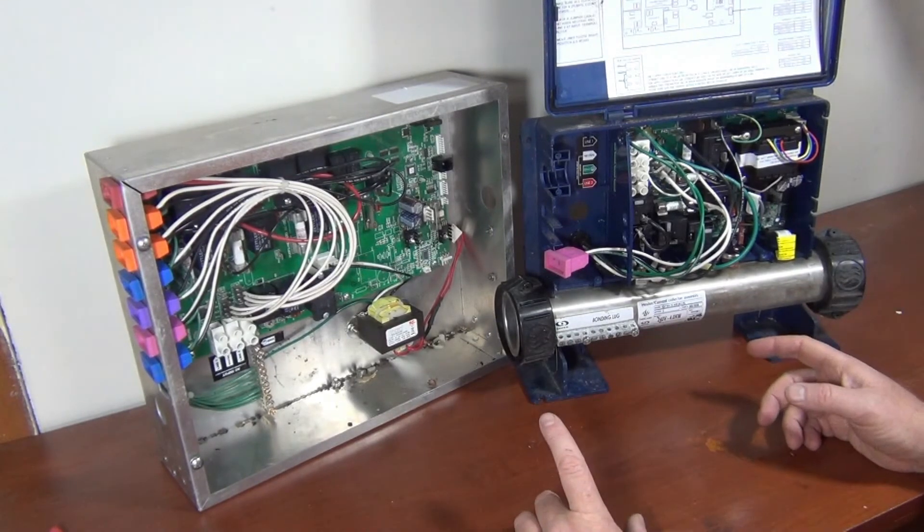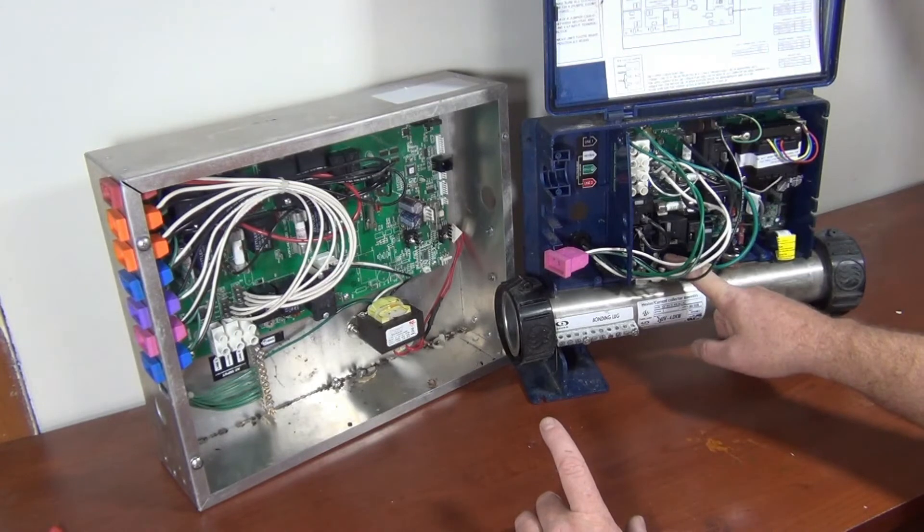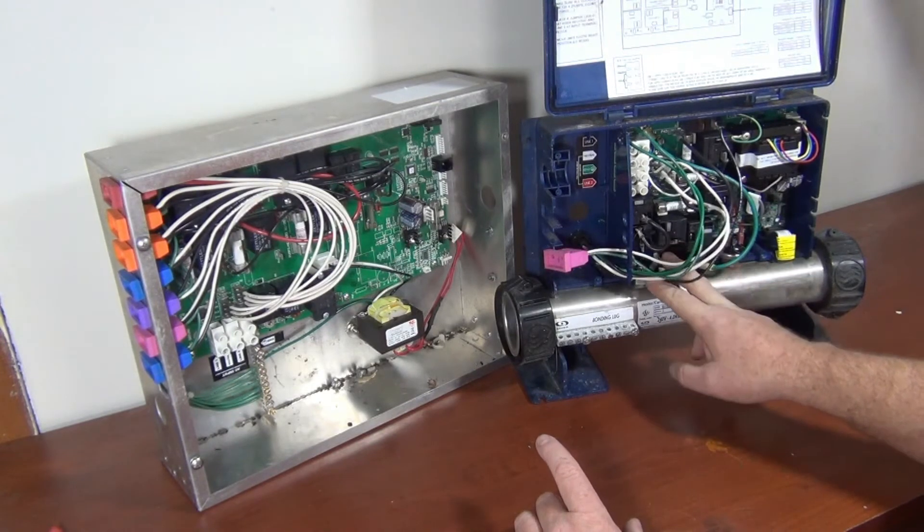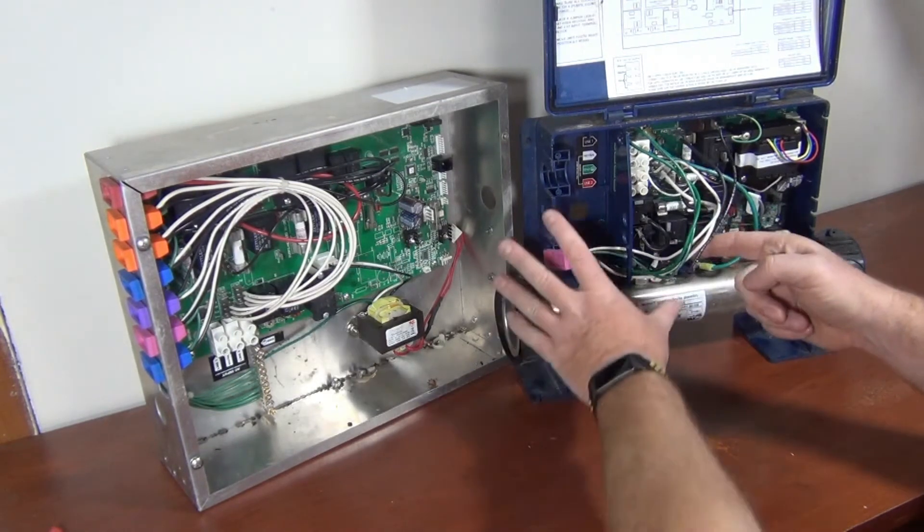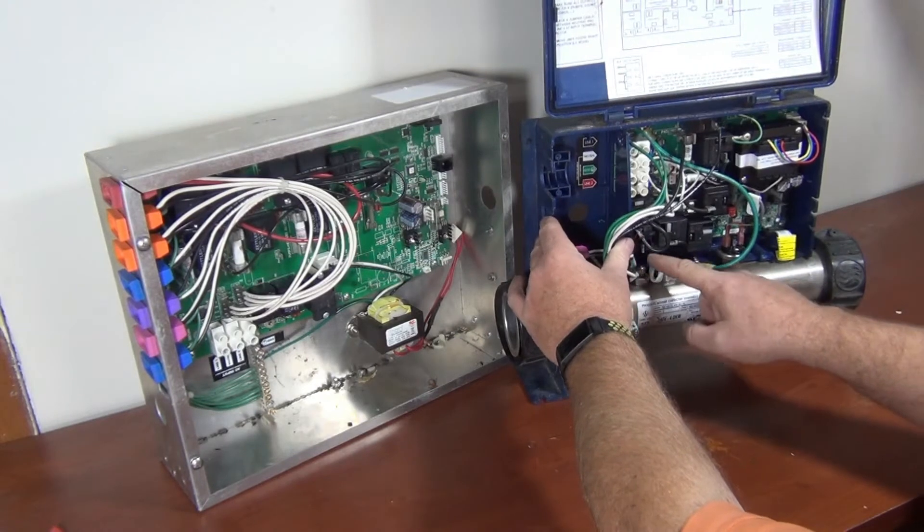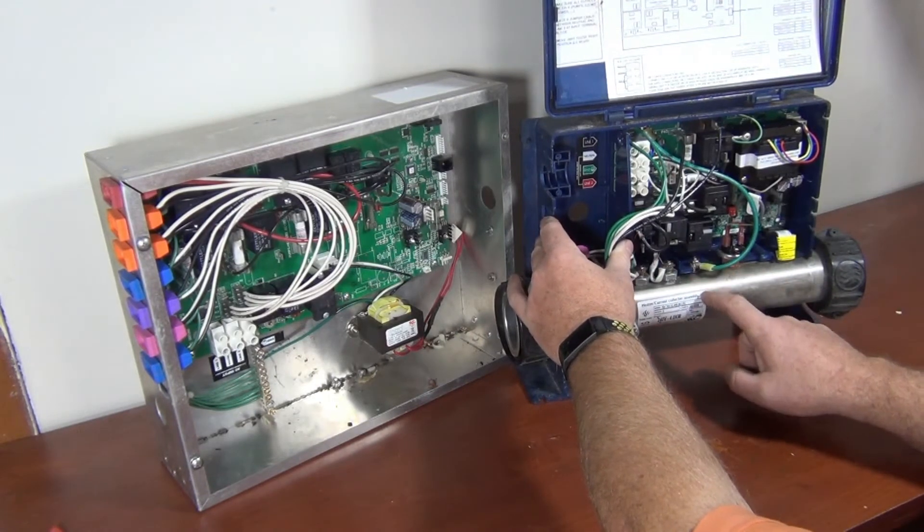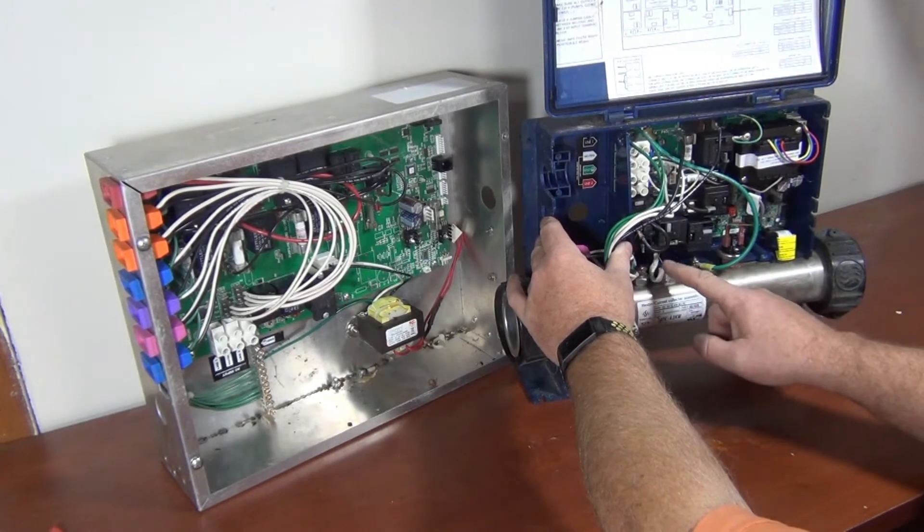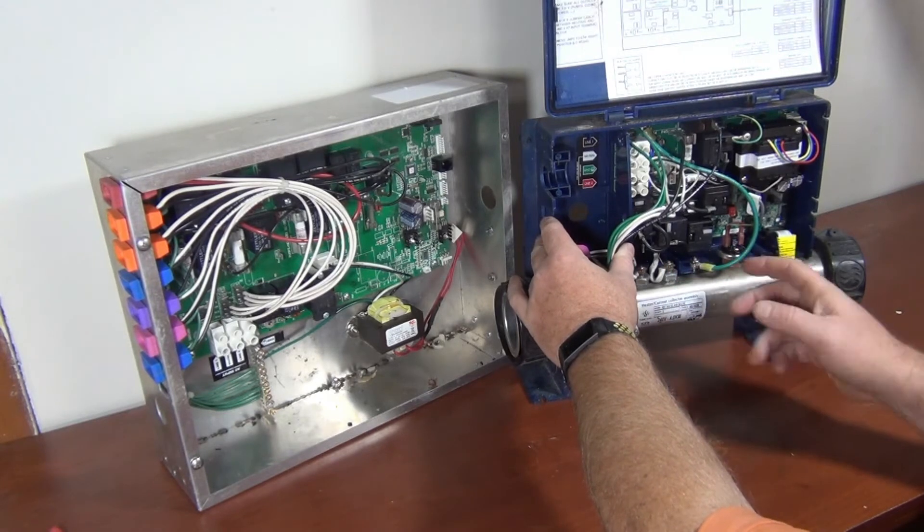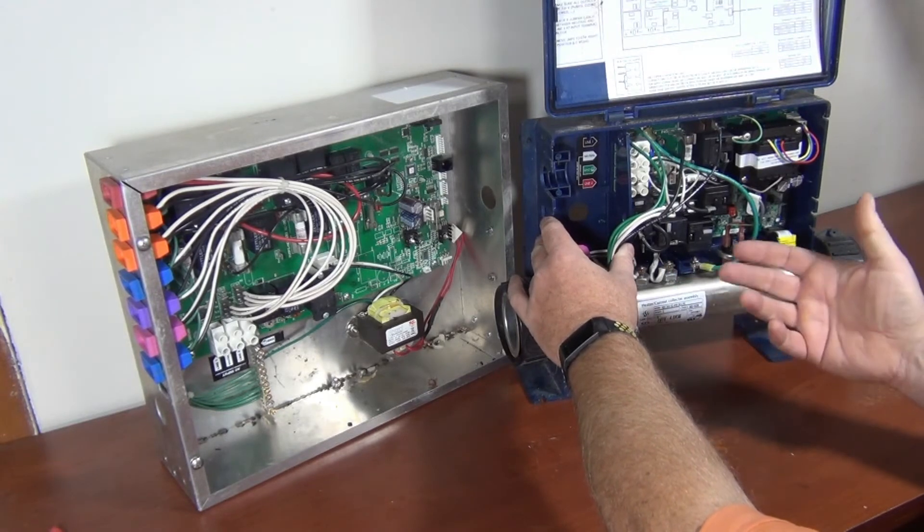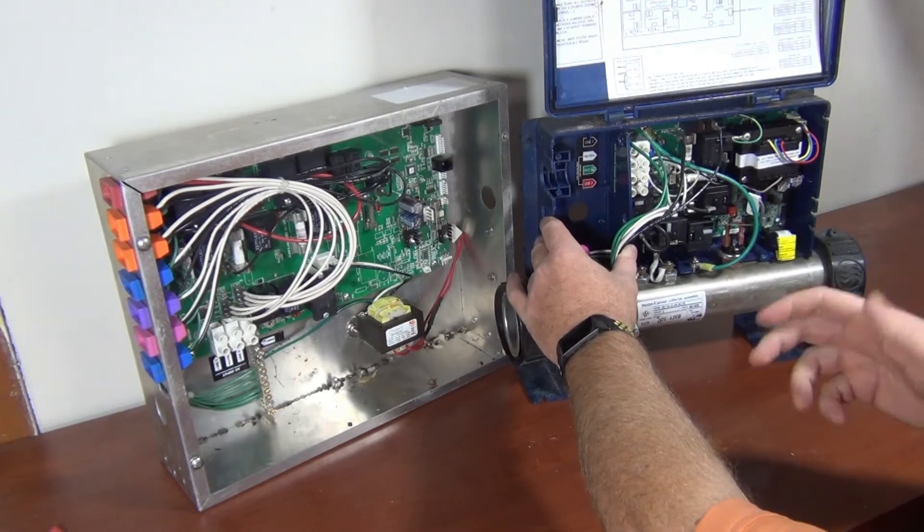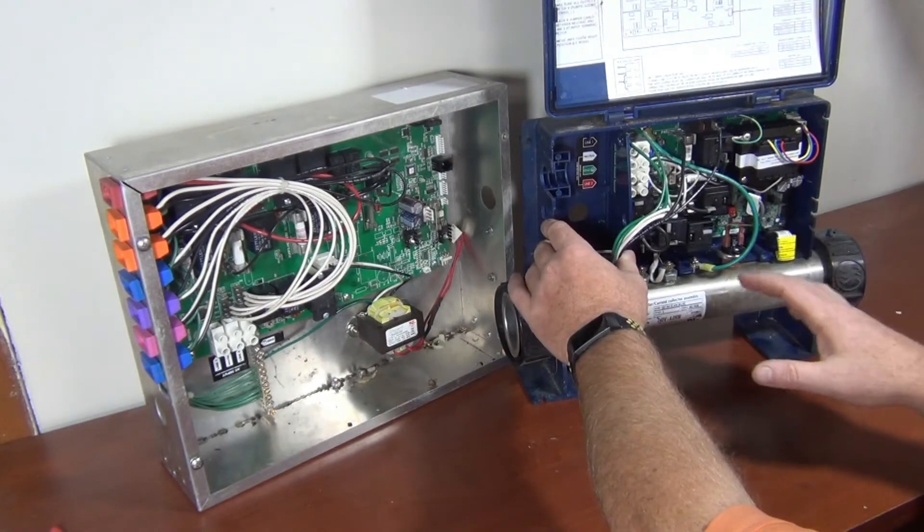So the first thing you're going to do is you're going to disconnect the heater element. So whatever style you have, but for this style, it's the two bolts on the heat tube. So disconnect this, move the wires out of the way. Make sure it's not touching anything if you have to put something on it, just make sure it's not touching anything.